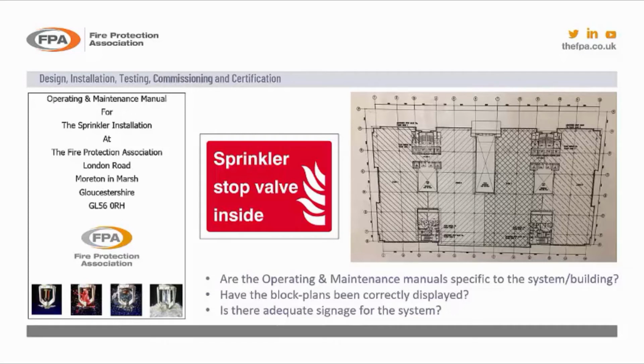The block plans, there's a requirement for the information that needs to go on the block plans. It needs to identify if they're zoned, it needs to identify where the water supplies are and what the water supplies are capable of and the stored water capacity. It needs to identify where the main isolating valves are or where the zone valves are. The alarm gong, what the design density is or what fire area it's protecting, and then by virtue of doing a block plan, normally coloured, unfortunately I've only shown you an example of a black and white one, but by hatch patterns or colouring it shows you the different zones and what they're being protected and where they're being protected.